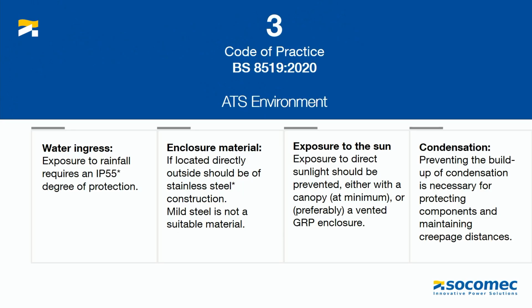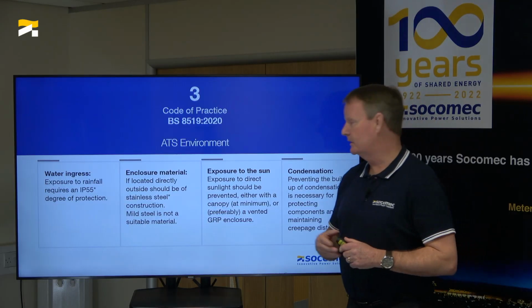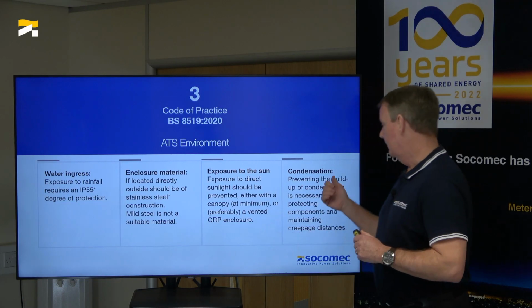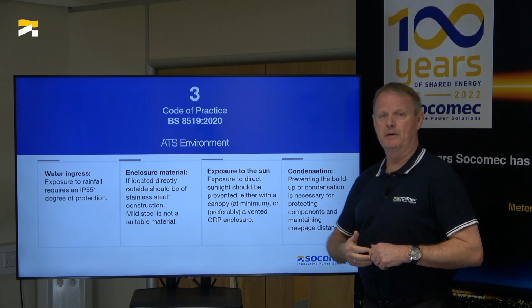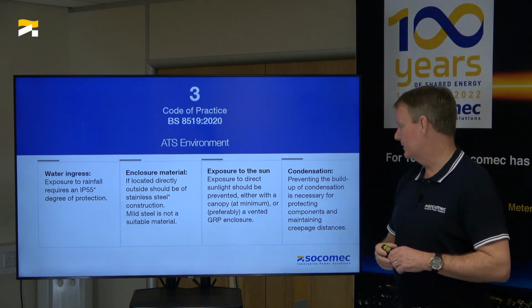More likely to worry about water ingress, because it does rain every now and again, especially in Wales, where Richard comes from. And then the other thing to be careful of is that if your IP rating is too high, you have the risk of condensation. So you need to put mitigations in place for condensation removal.